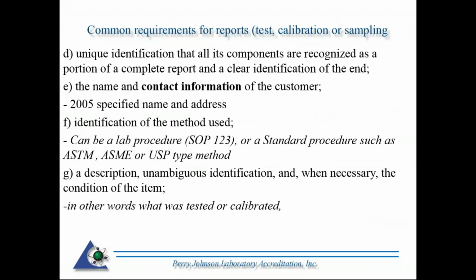Unique identification, so that all its components are recognized as a portion of a complete report, and a clear identification of the end of the report. So the unique identifier is going to be unique to that particular test, calibration, or sampling report. Most of the time I'll see something such as a certificate number or a test number that's unique.